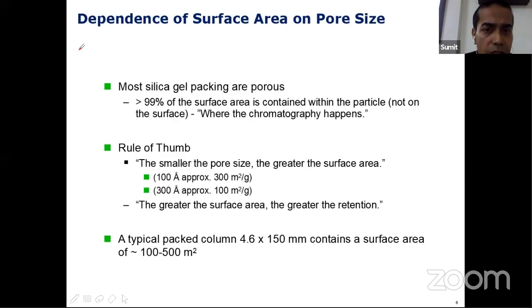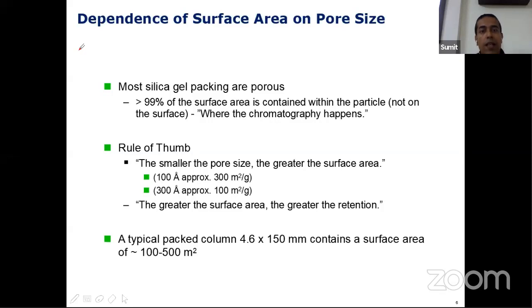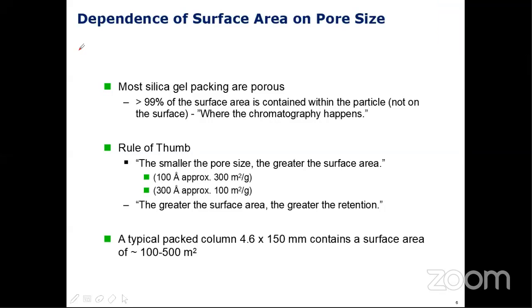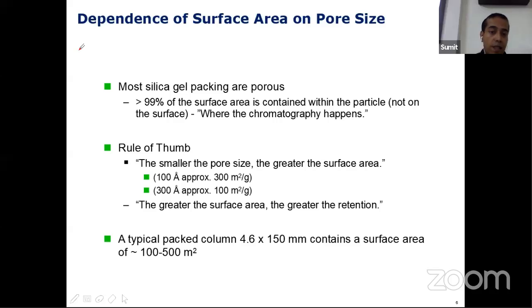Most silica gel packings are porous. Previously we used non-porous particles, but nowadays that is not the case because of the several advantages of porous particles. The pore is the part of the particle where the chromatography happens — more than 99% of the surface area is contained within the particle; it doesn't happen on the surface. That is why pore size is so important. The rule of thumb is: the smaller the pore size, the greater the surface area, which is pure physics. And the greater the surface area, the greater the retention, and therefore you can expect better resolution. So that's why the chemistry is correlated with the pore size.